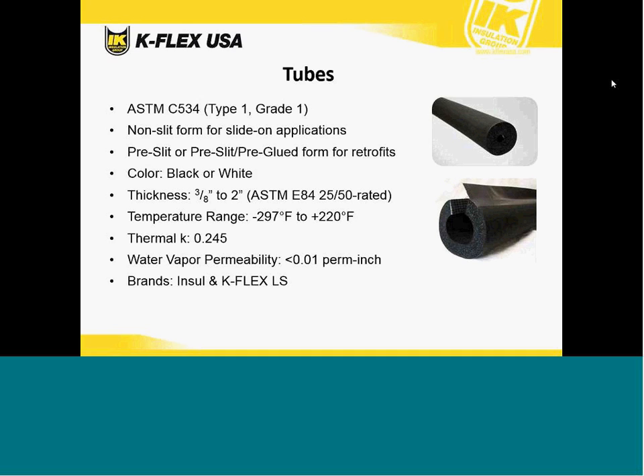Available in black or white, and in thickness from 3/8 of an inch up to 2 inches, and it's ASTM E84 25/50 all the way up to 2 inches. The temperature range for this product is from -297 Fahrenheit up to 220. The thermal conductivity is 0.245, and the vapor permeability is less than 0.01 perm-inch, which, as you know, is well below the ASHRAE Class 1 vapor retarder line.